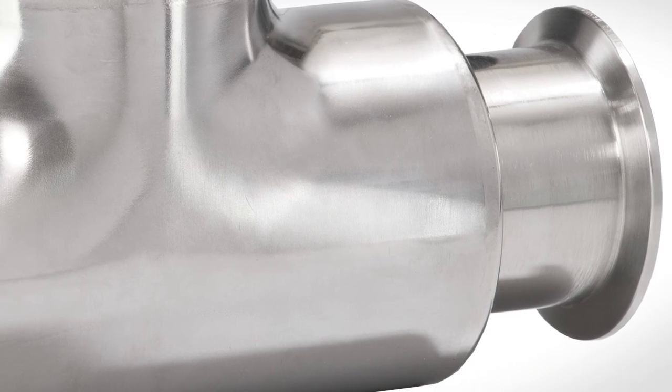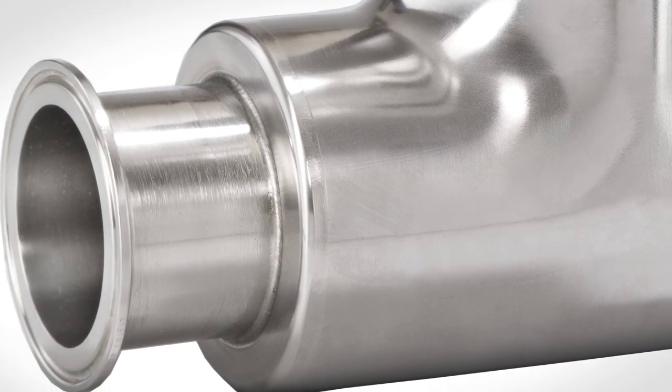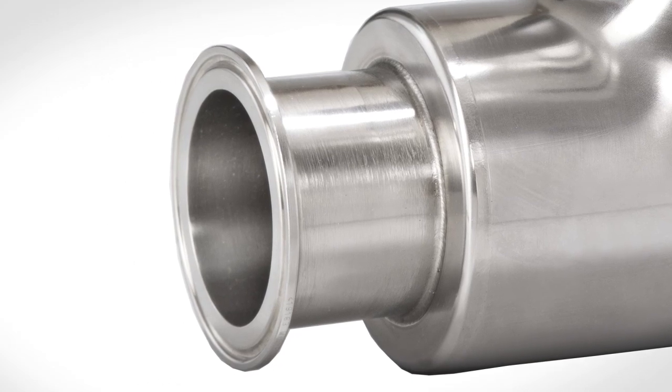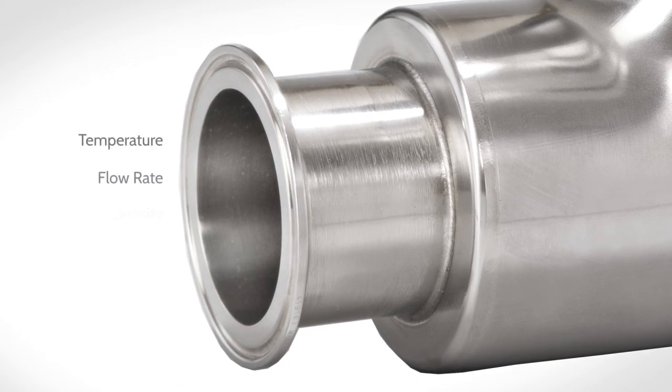Interdigital transducers, located on the outside of the measuring tube, are used both as transmitters and receivers of a signal that behaves like a seismic wave, which is used to measure the temperature, flow rate, and density of the medium passing through it.